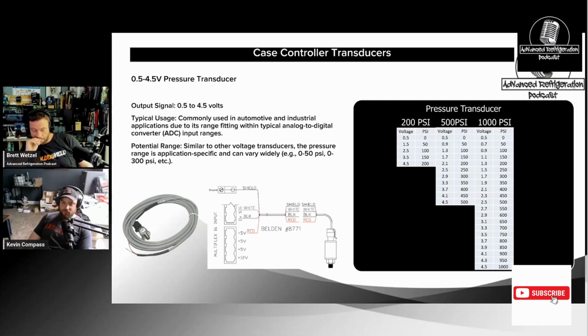If I see one and I'm checking it and it's 3.5 and it's not reading 150, I'm going right to the setup. Is it set up and scaled properly? Is it set to the right pressure? Does somebody have an offset in there? Because generally, transducers either read right or they read way off — they're not 3 to 5 pounds off. That 3 to 5 pounds is your gauges. Honestly, I trust most transducers more than most gauges.